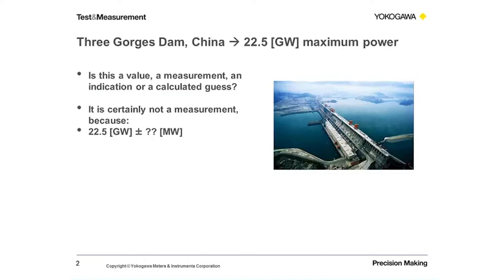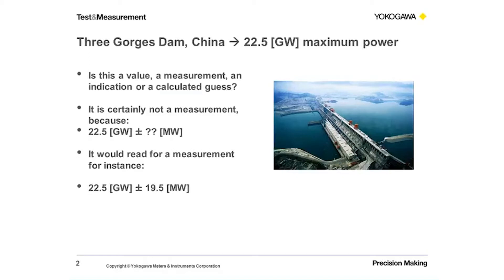If it was a measurement — which it certainly is not — it would read 22.5 gigawatt plus minus an uncertainty. For example, if we calculated using one of our power analyzers, we would read 22.5 gigawatt plus minus almost 20 megawatts. This uncertainty cannot be ignored because as energy generated from this dam is traded every day, somebody will have to account for the right loss for this uncertainty when trading the energy. So knowing the uncertainty is very important.